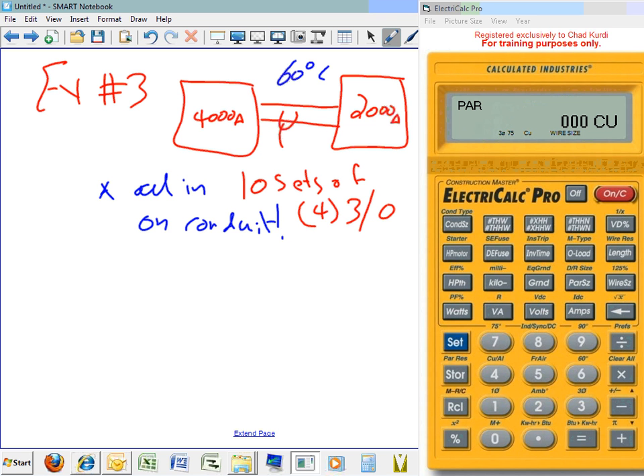But how many current-carrying conductors out of them? Well, the neutral is not counting because these are panels. The neutral at that level is not carrying current, it's carrying just the balance. So the first thing you need to do is current-carrying conductors equal 10 of them times 3, because of the 3 phase, equals 30. So now I know that I have to do it based on 30 current-carrying conductors and also temperature. Let's go do that.